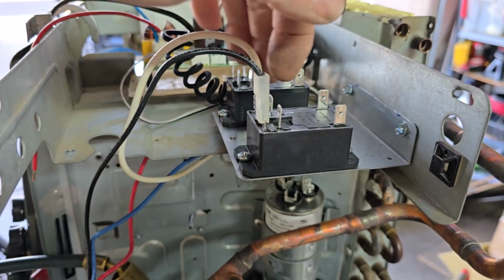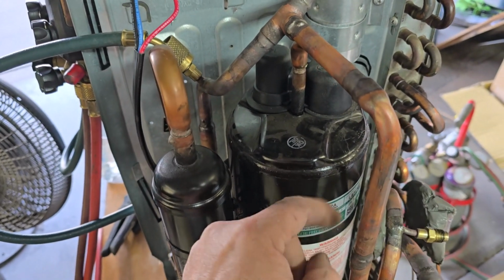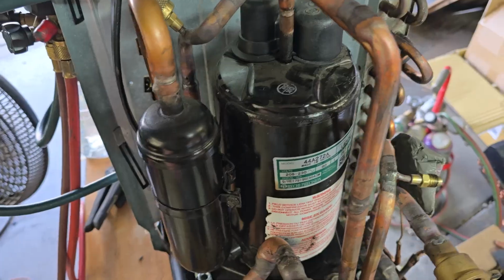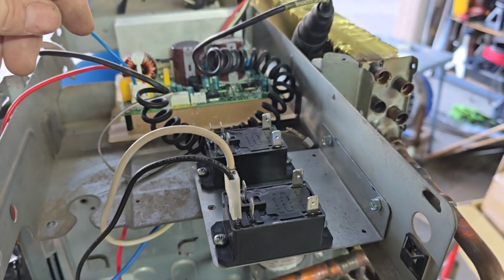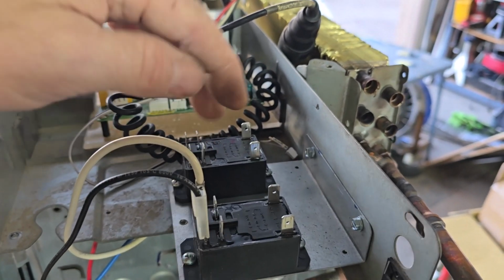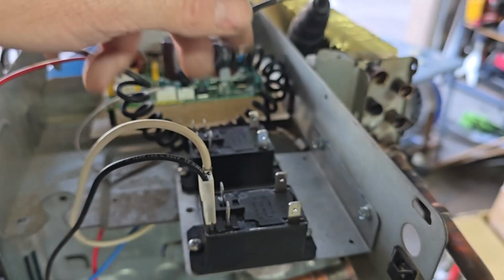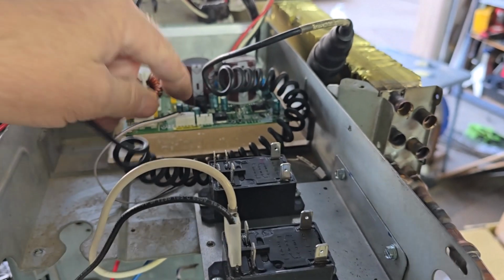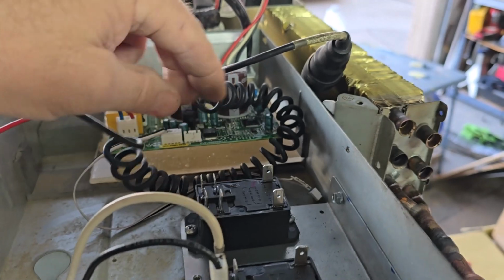This one here is going to close the 2 poles to the 240-volt compressor. And then this one here—I could have used one contact for the compressor and one for the fan, but since it's low voltage control, I don't want them anywhere near each other, so this one's just going to switch on the fan.